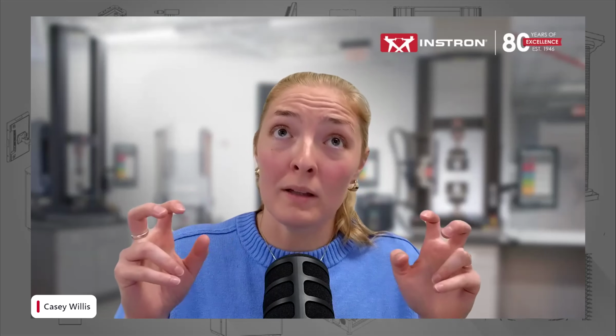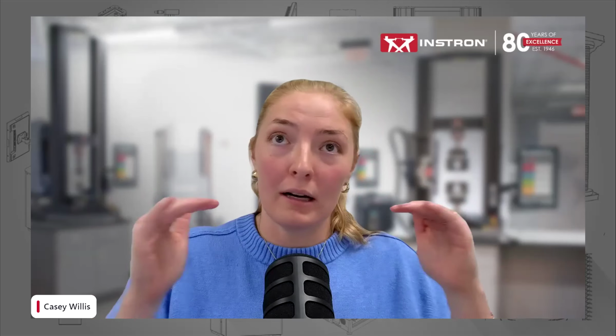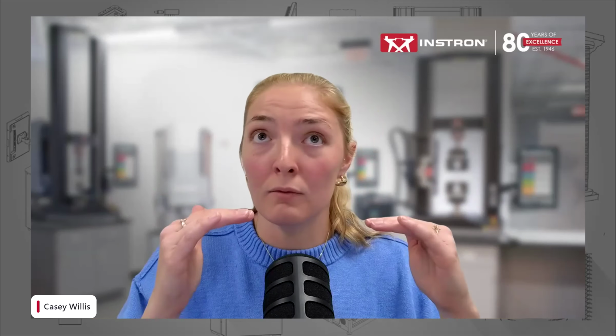Our spec sheets are on our website. As far as performance, our extensometers are capable of meeting class B1 for ASTM or 0.5 for ISO. So it's really just your preference, what works best for your lab, what's within your budget.